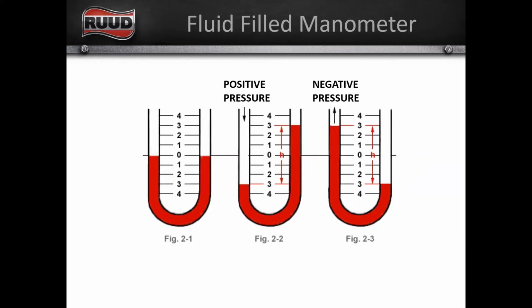And if we take that same tap and we move it to the negative side, or to our return, where we're pulling the air into the blower, that negative pressure pulls that column of water up by the same amount in this example. So in our figure 2-3, we have negative 3 inches, or 3 inches of negative pressure. And that's really what we're doing when we're checking static pressure. We're checking essentially how hard we are pushing or pulling on that column of water, or that virtual column of water if we're using an electronic gauge or a dial. The measurement scale is the same, just the way we measure it is different.